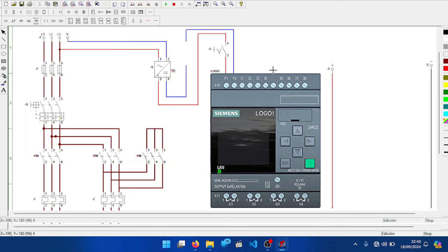to start our process. So I'll have a normally open contact there to represent the start button, then a normally closed contact to represent the stop button. Then I'll have a coil to represent the main contactor. Then I'll add hold on, or what's called the latching there. Then let's just connect them.